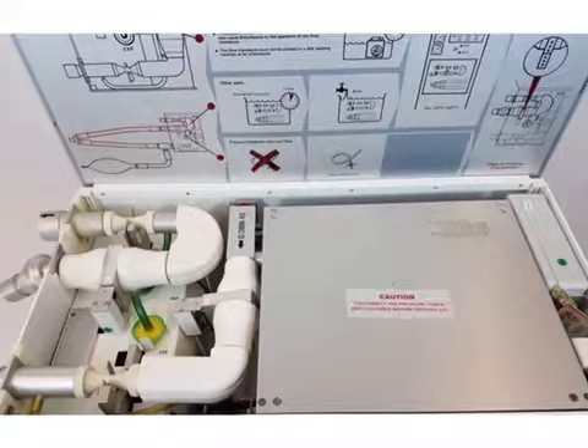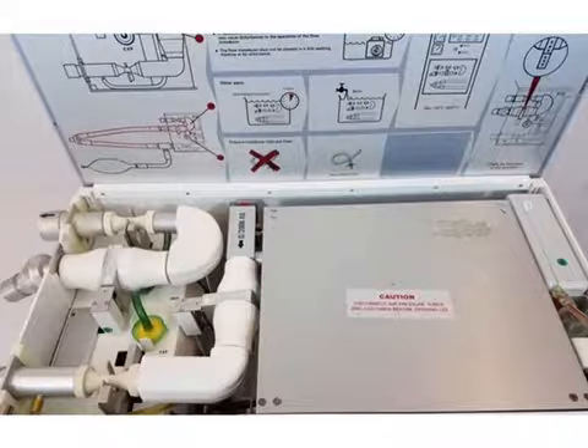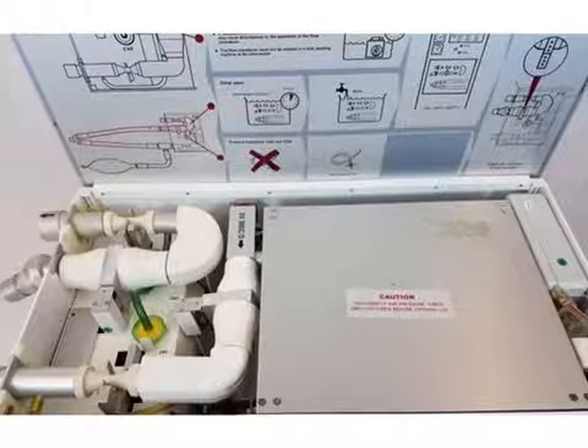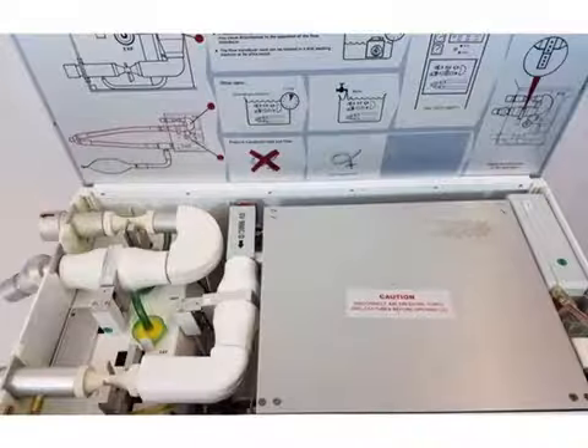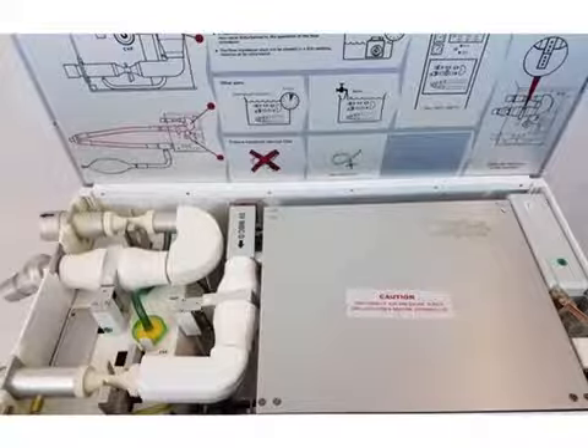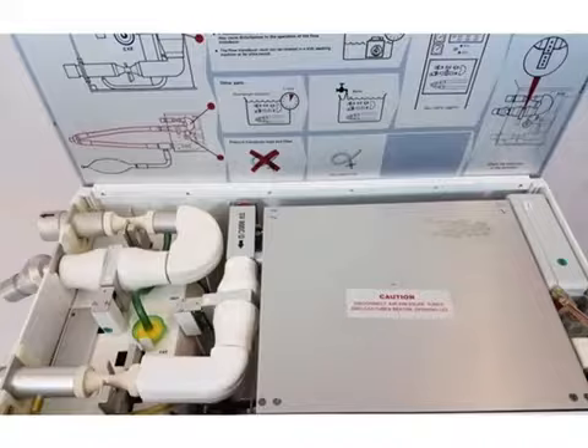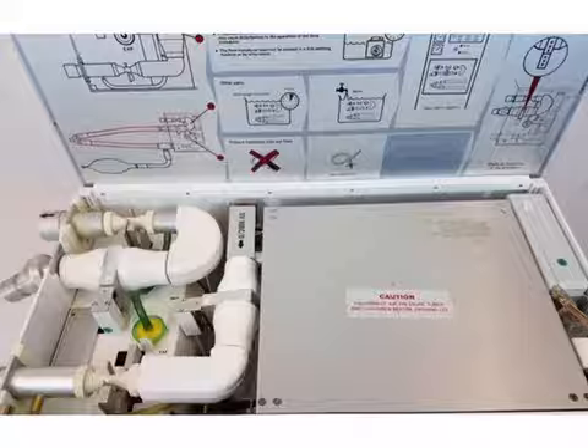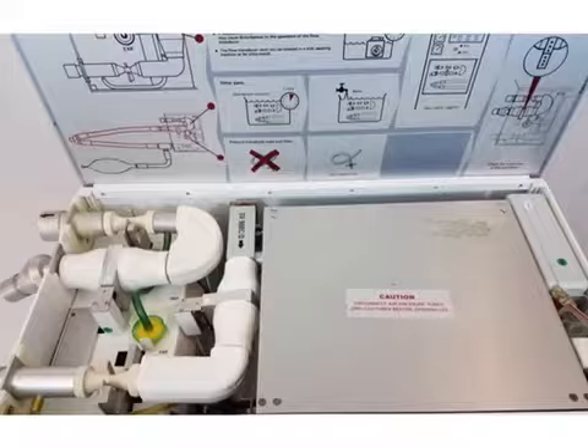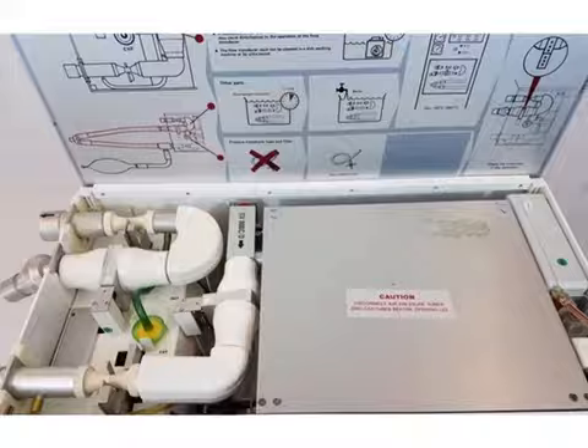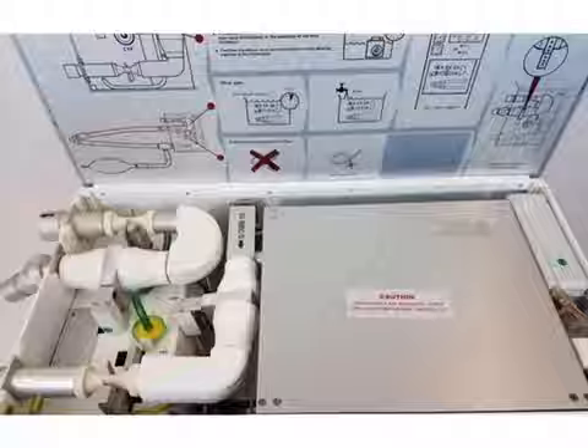Now if we open the hood of the machine, you can see the pneumatics. What we're going to do is look at the lower right-hand portion of the screen over here. From this picture, it's kind of hard to see, but from the gas inlets, it comes over here. The gas supply is regulated by a valve, so that a constant pressure is maintained in the bellows. So it goes from the gas connection to this valve. Then the gas travels this way up, and it goes to here, and that's the O2 cell. So it measures the oxygen concentration of the gas.